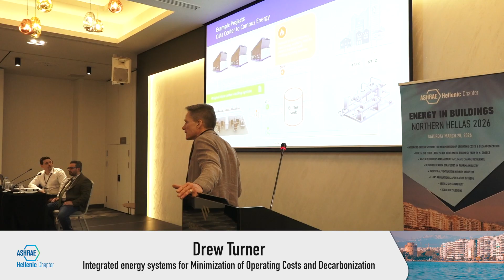And so what we try to point out is, back on the hydronic system, if it is hydronic, then it's really easy to tie in to recover that heat, because all we do is tie into the cooling return line to take that and bypass it through a water-to-water heat pump that then boosts it up to replace the energy going into the campus energy system. So it becomes a very simple retrofit. You're not replacing anything, you're just adding to it. That then provides the base load cooling for the data center system. Those existing chillers were installed about 7 years ago, and this is based on an actual use case. This retrofit was done about 4 years ago. And these are still there, but they just act as backup, operating basically like the backup power system, operating maybe 5% of the time a year, anytime we're not recovering enough heat to drive enough cooling to cover the cooling of the data center itself.